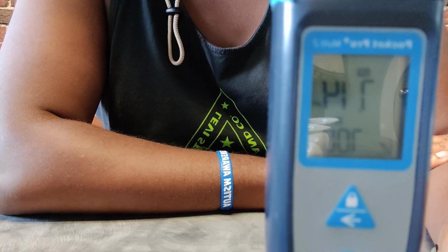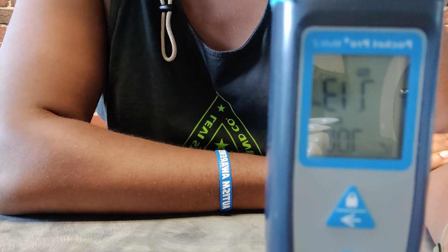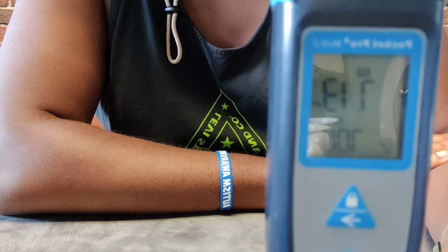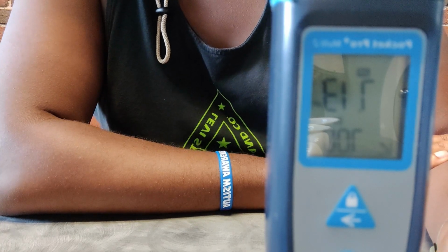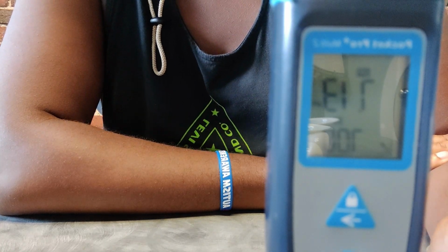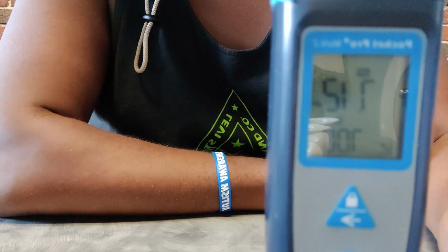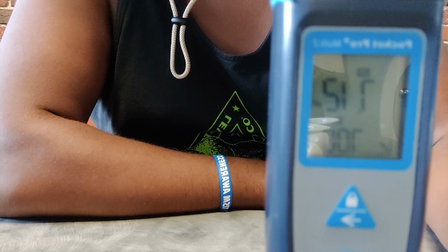The numbers on the top row should be allowed to settle for a moment. This could vary by machine and take as little as 5 seconds to well over 30. The top row doesn't need to read 7.01, it just needs to stop at a number. You want the number on the top row to be stable. If the number in the 1s and 10s column are stable, so in this case the 7 and the 1, but the number in the hundreds column is moving up or down, but very slightly or very slowly as it did just now, the 5, that's okay too.